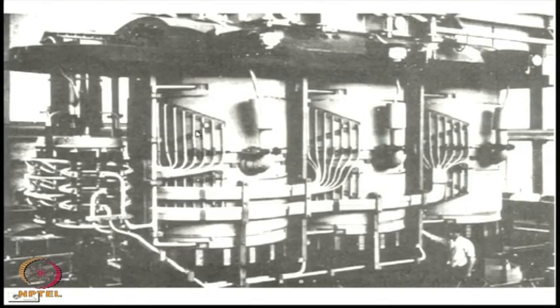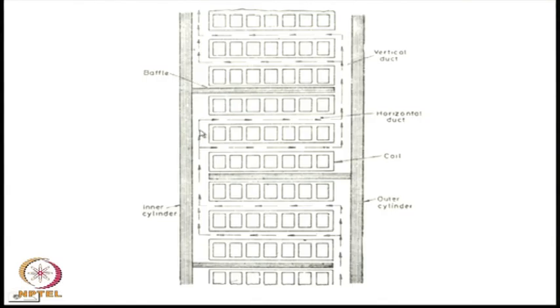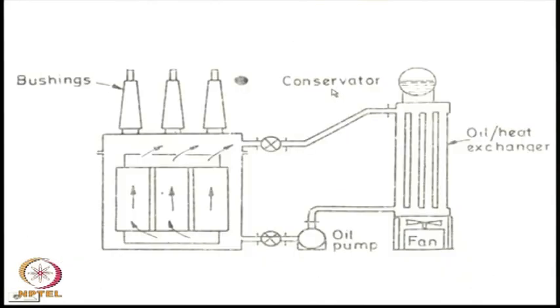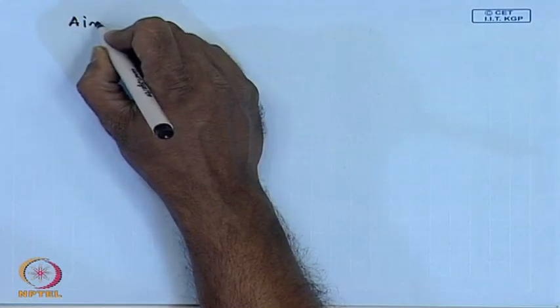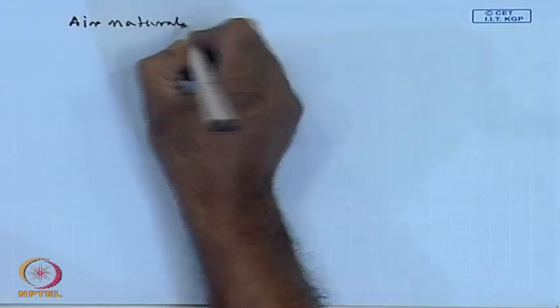We have mentioned in one of these slides that it is necessary to circulate cooling fluid through the windings and the core of the transformer in order to prevent the temperature of the transformer rising to a very high level. Now, there are different methods of cooling. For a small dry type transformer, it is usually not necessary to use any separate cooling medium. The transformer is left outside, and the ambient air is sufficient to cool it. This is called air natural cooling, or AN.